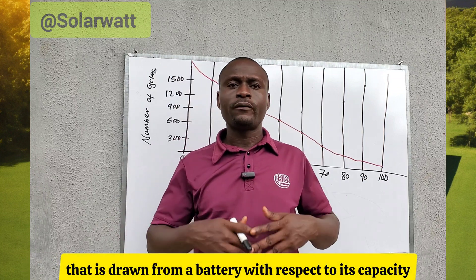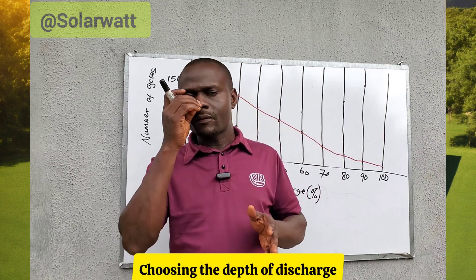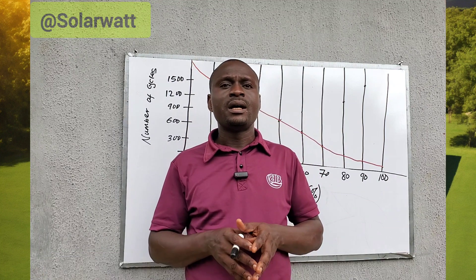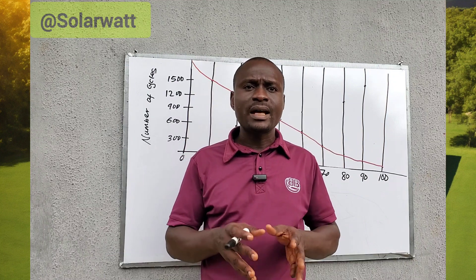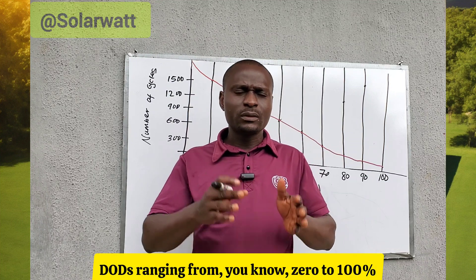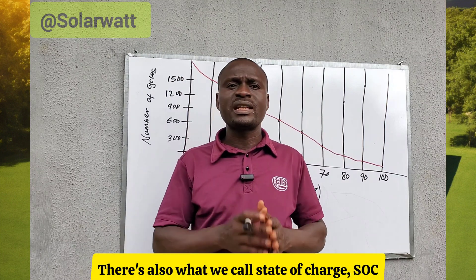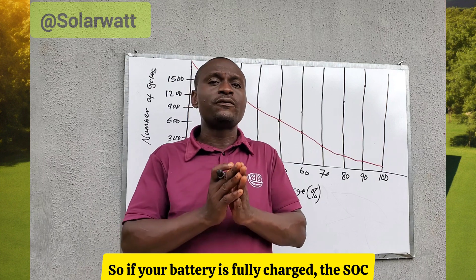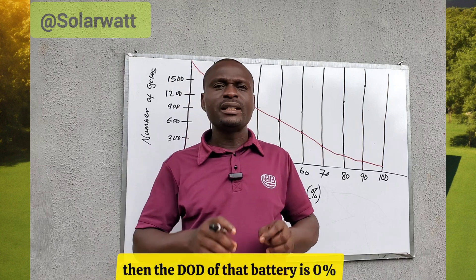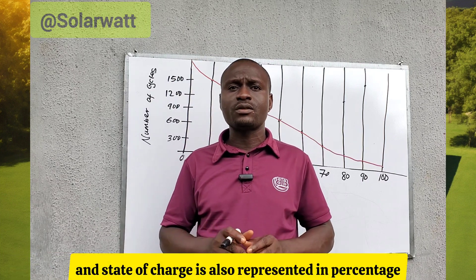Choosing the depth of discharge of a battery is very important because it is a key factor when sizing a battery bank — it determines the size of the battery bank. DoD values range from 0 to 100. The DoD is the opposite of state of charge (SoC). If your battery is fully charged, the SoC is 100% and the DoD is 0%.